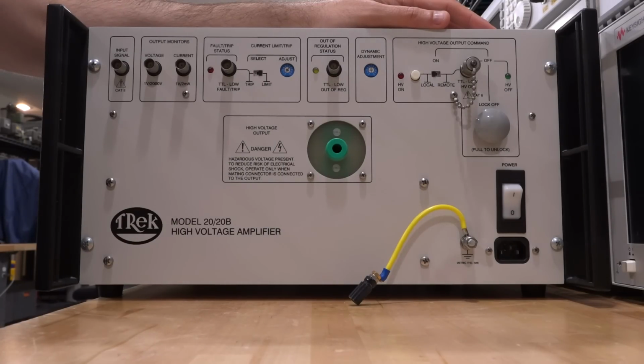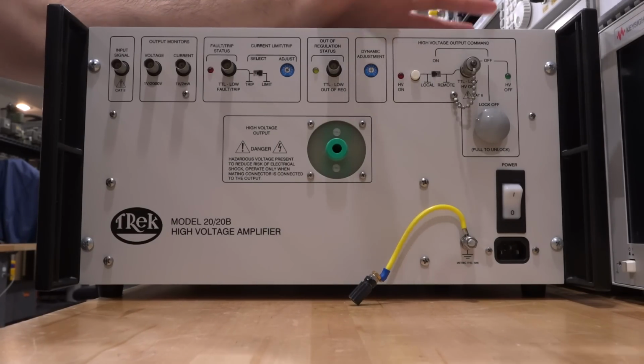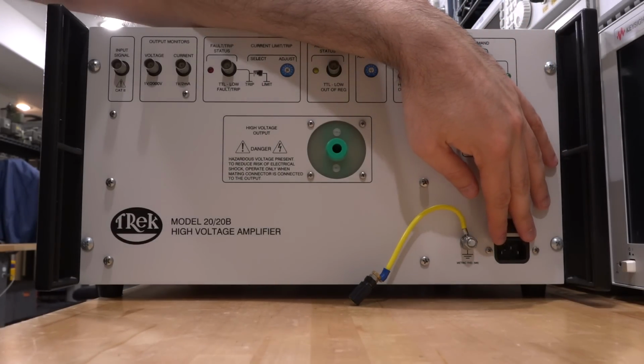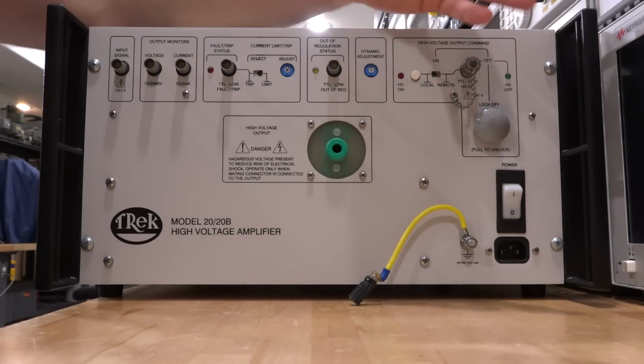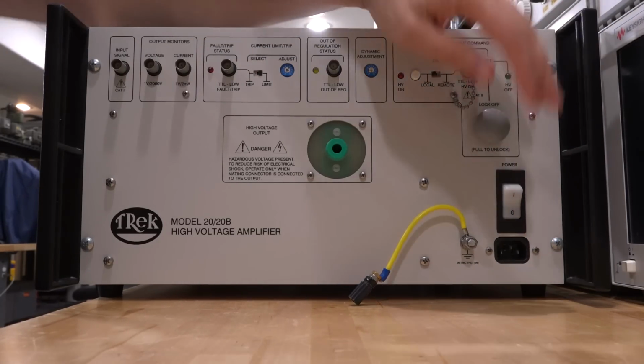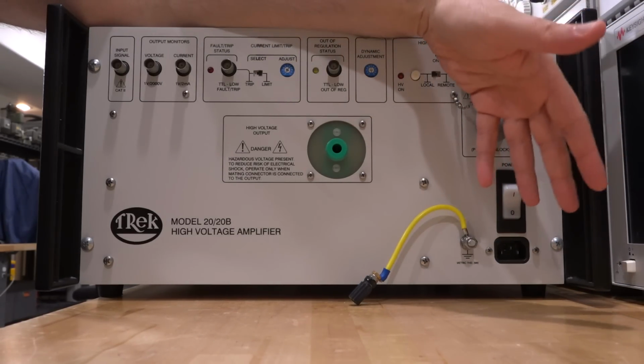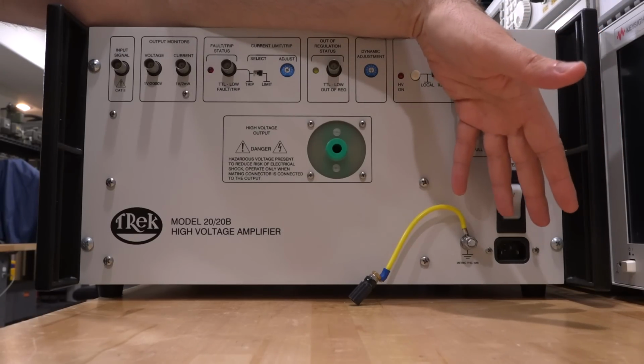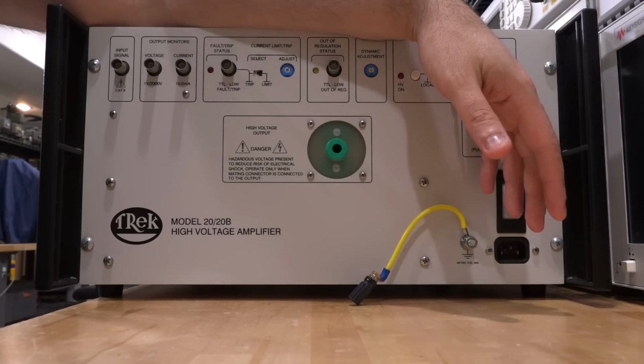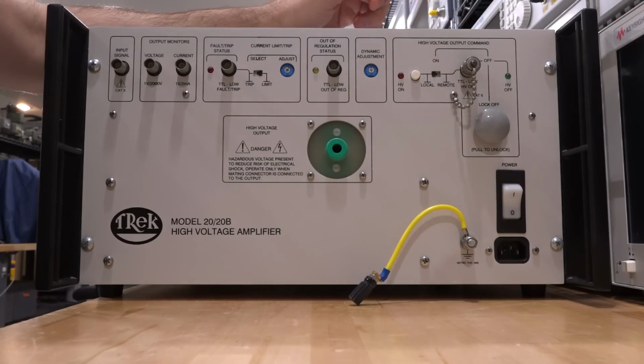And here's the front of this instrument, and as you can see, it's pretty gigantic and it weighs a lot. The AC input is interestingly in the front of the unit. That's because the high voltage power supplies are in the back. In a way, this AC input is the lowest AC signal in this entire unit, because after this it goes into high voltage power supplies around 20,000 volts. And then we do have our power switch, of course, right there.